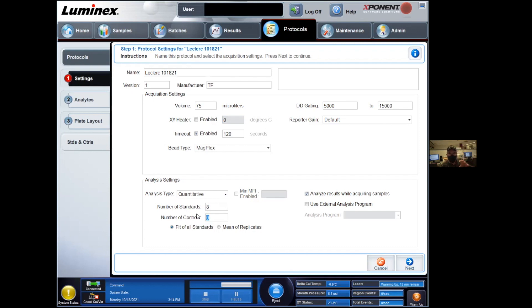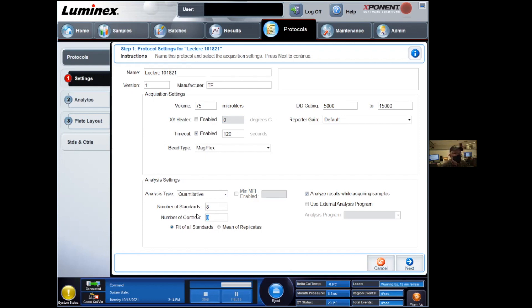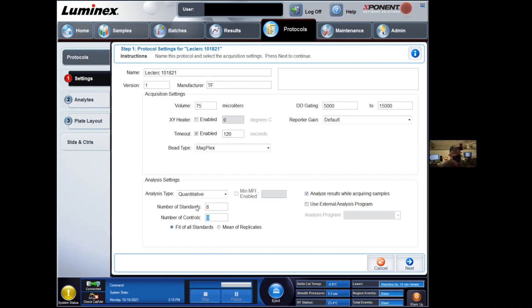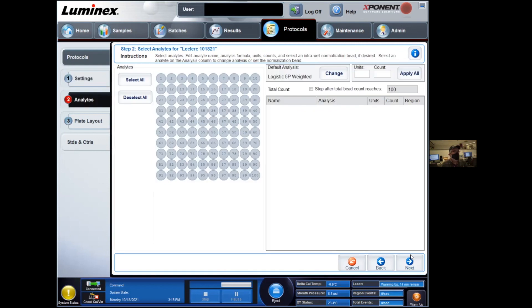Controls, we're talking about any control that was provided by a manufacturer within the kit. They have a specific range of expression that it should reach for you to know that the kit is working properly. And again, I'm just going to enter them as a regular sample. And later on, when you do your analysis, you can check on the values of these controls and see if they match whatever the manufacturer wanted them to.